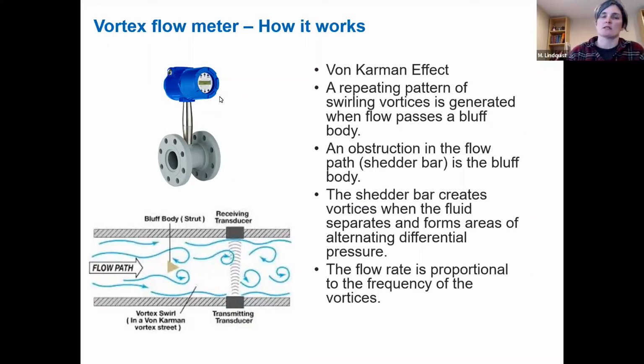The problem you're going to run into is it's generally pipe diameters up and down, so they're actually looking at flow and also pipe size. And then the big thing you run into when selecting a type is how much straight pipe can you find to install that meter. One of the benefits of the turbine meter is that it needs less straight pipe. The vortex flow meters, the flow meters that you saw in the photos earlier, can need larger runs of straight pipe. So it's all going to be dependent on the meter type, and each manufacturer is also different as to how many diameters of straight pipe upstream and downstream are required.